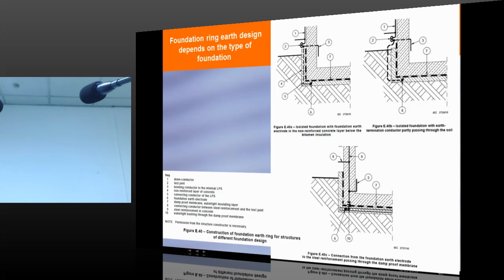So this is the insulation, the water insulation which is provided. And in this case, you have to think of extending the earthing, and one of the methods is that under the building, under the insulation, you can have a mat. So this is another way. Under the mat there is a kind of RCC installation. So different methods are explained, but when you design this kind of building, you need to really buy the standard and go through it.